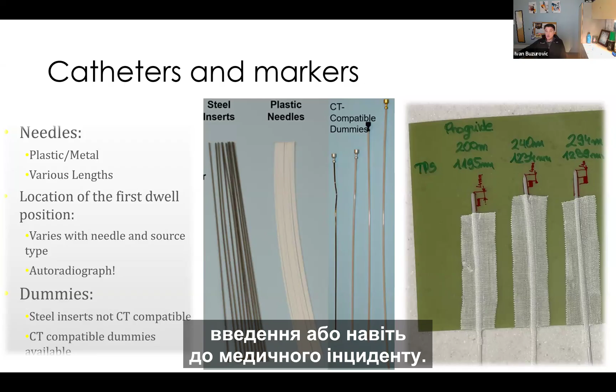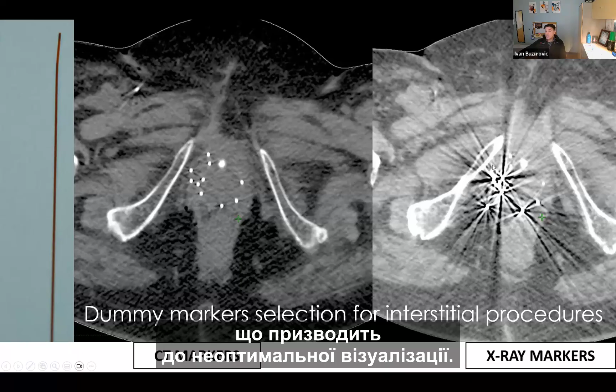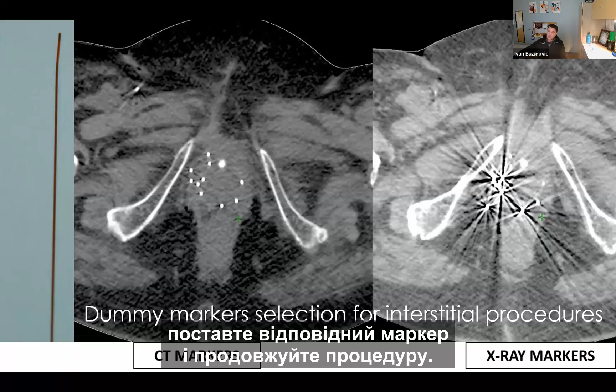This is one Gafchromic film when we deliver the virtual treatment plan and try to assess the accuracy and to assess proper reconstruction. If the needle is not properly reconstructed or calibrated, we can physically displace the whole implant. That can lead to a misadministration or even to a medical event. The dummy marker or proper markers should always be used. For instance, I will show you what can happen if these non-CT-based markers are used for a procedure. You can see that the quality of a CT scan degrades significantly, and that leads to suboptimal visualization. So in this case, we had to take out the wrong marker, put in the right marker, and continue with the procedure.